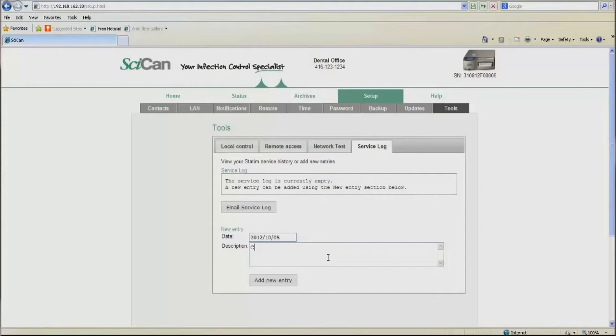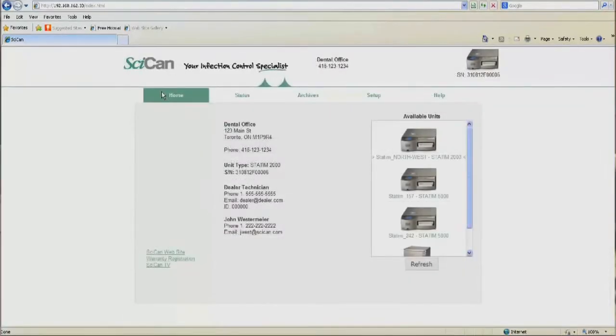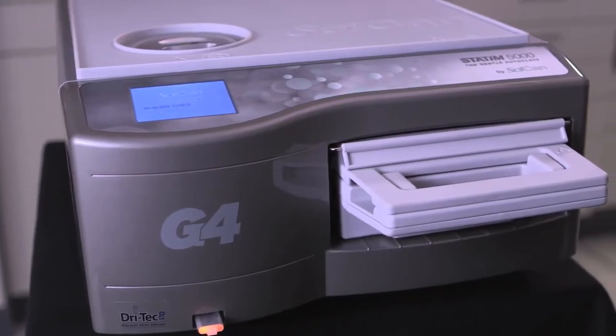Service techs can also record any work done on the G4's web portal, allowing all techs to view the repair history and streamline repairs. As software upgrades become available, SciCan initiates online firmware updates, ensuring your Statim continues to offer the most sophisticated user interface the industry has to offer.